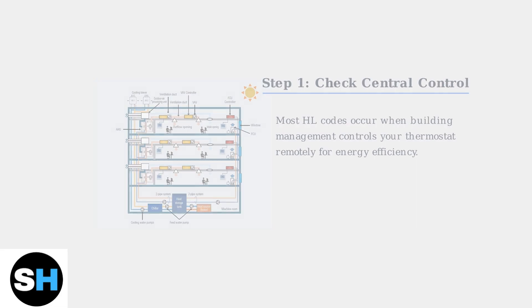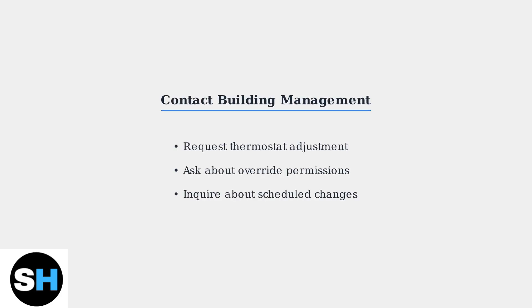The first step in troubleshooting the HL code is to determine if your building uses a central HVAC control system. This is the most common cause of the hard lock error. If your building does have central control, contact your building management or property manager.